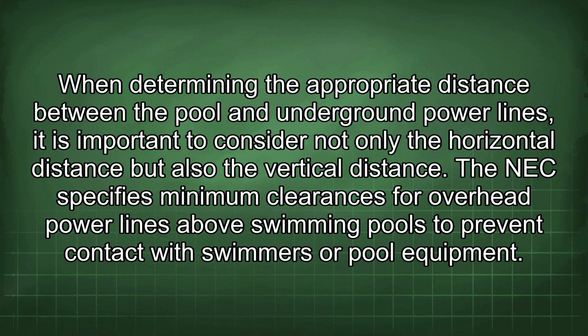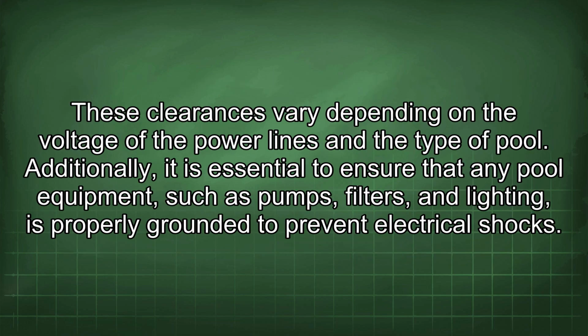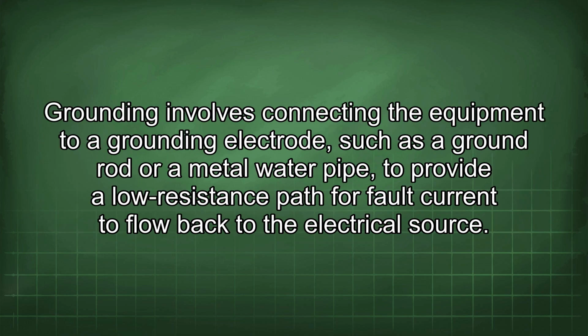The NEC specifies minimum clearances for overhead power lines above swimming pools to prevent contact with swimmers or pool equipment. These clearances vary depending on the voltage of the power lines and the type of pool. Additionally, it is essential to ensure that any pool equipment, such as pumps, filters, and lighting, is properly grounded to prevent electrical shocks. Grounding involves connecting the equipment to a grounding electrode, such as a ground rod or a metal water pipe, to provide a low resistance path for fault current to flow back to the electrical source.